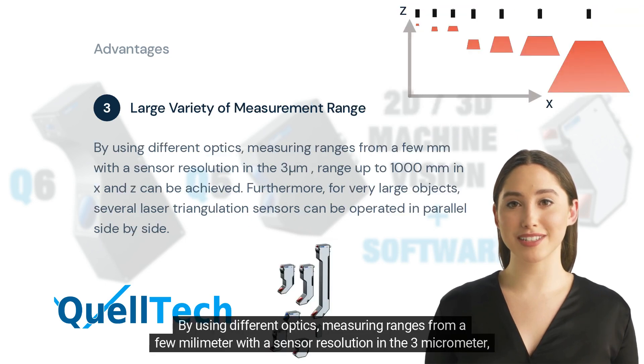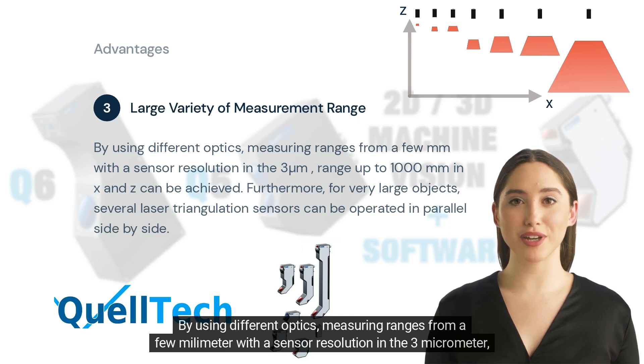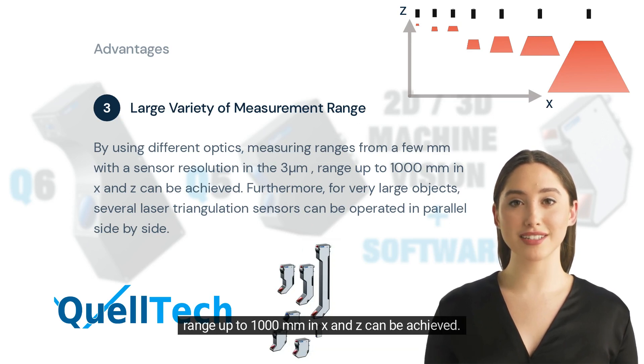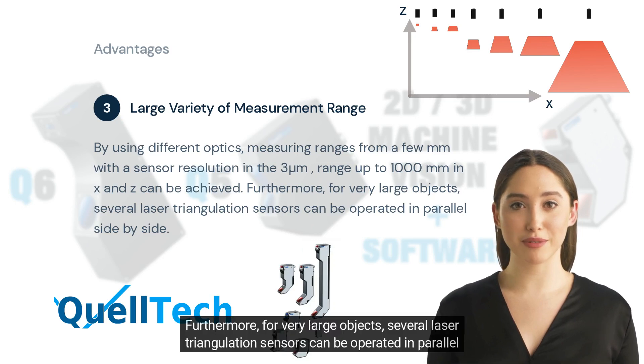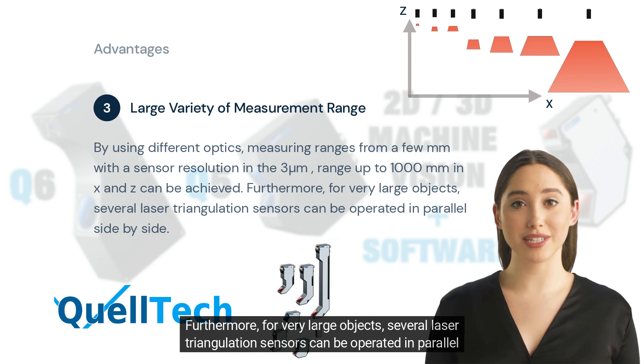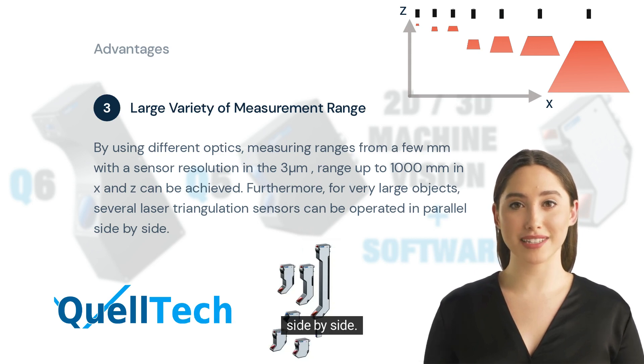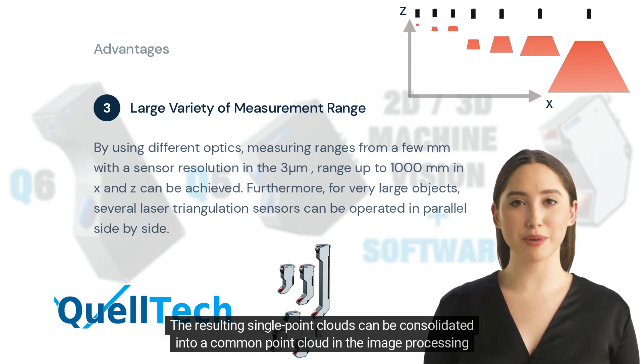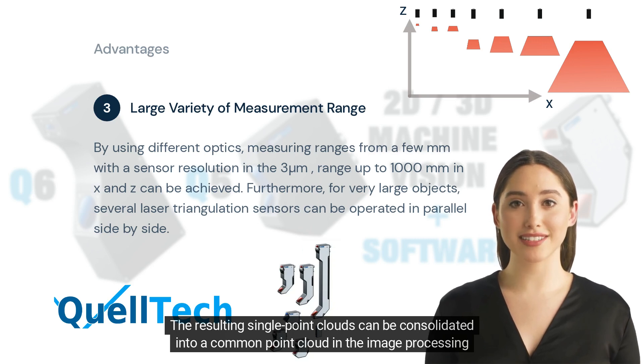By using different optics, measuring ranges from a few millimeters with a sensor resolution in the 3 micrometer range, up to 1000 millimeters in X and Z, can be achieved. Furthermore, for very large objects, several laser triangulation sensors can be operated in parallel side by side. The resulting single point clouds can be consolidated into a common point cloud in the image processing software.